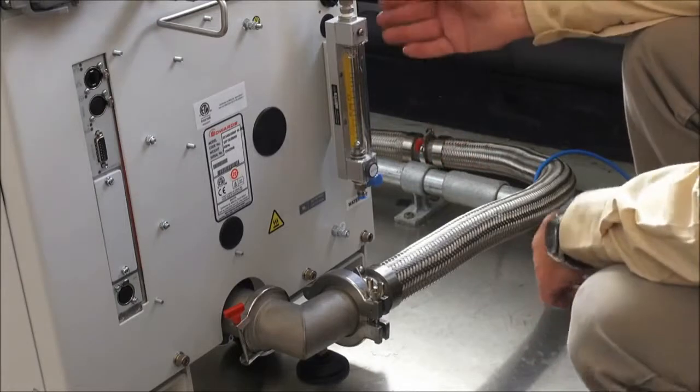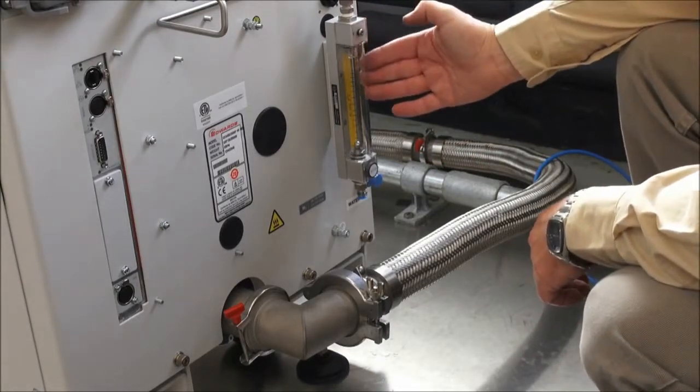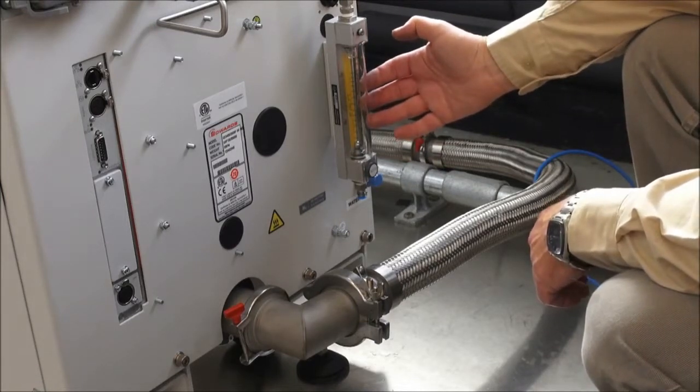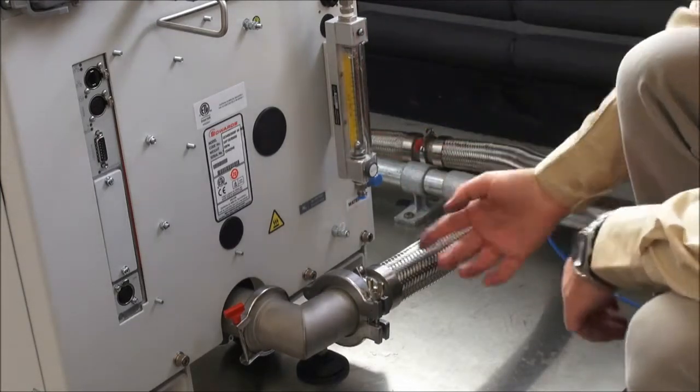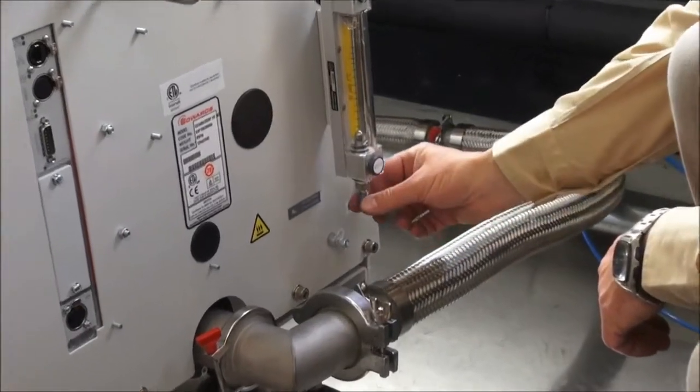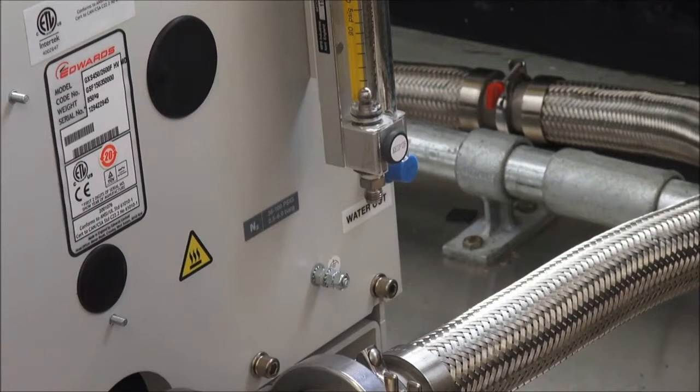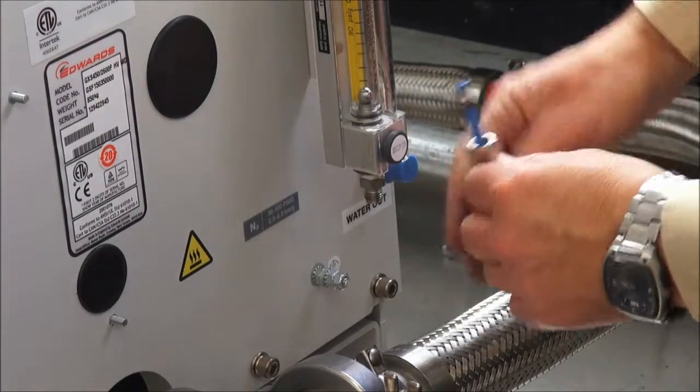Now we need to connect to the utilities supplies. There is a flow meter or rotameter at the rear of every GXS, as all GXS pumps use purge gas in varying amounts. The connector on this rotameter is a quarter inch female Swagelok. Always remove the blue shipping stopper from this fitting even if your purge gas supply is not yet ready.